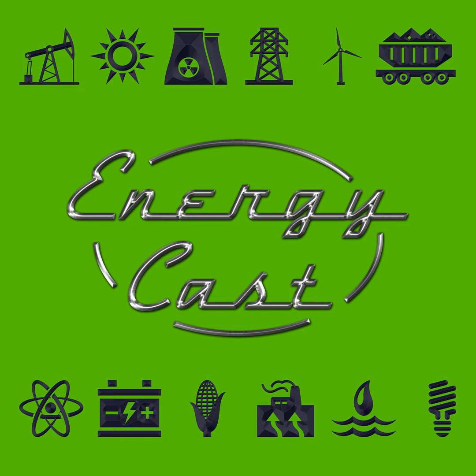You typically have to have the charging technology, and what they're actually talking about here gets into more of a grid-tied storage type application. For instantaneous response, something like nickel zinc would be ideal. For longer term things, flow batteries or zinc manganese would be better technologies. You generally have equipment that's designed specifically to tie you to the grid, both the charging side and the inverter side, and it has to be rated for grid-tied applications. So it's a rather specialized area. It's not something you're going to go pick an off-the-shelf transformer or inverter to make work.